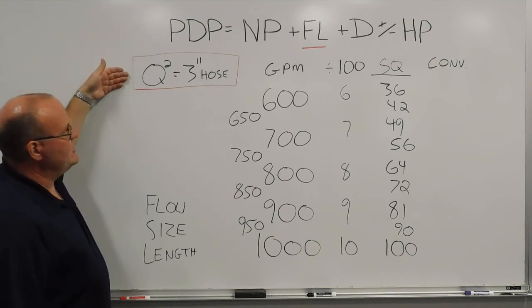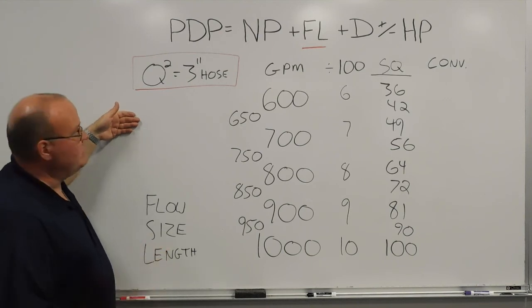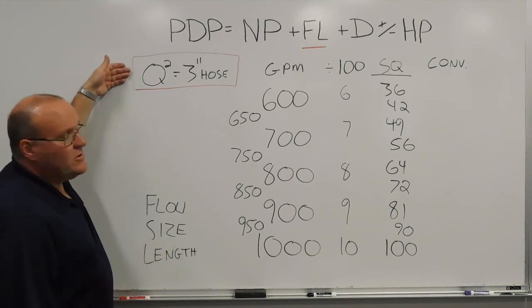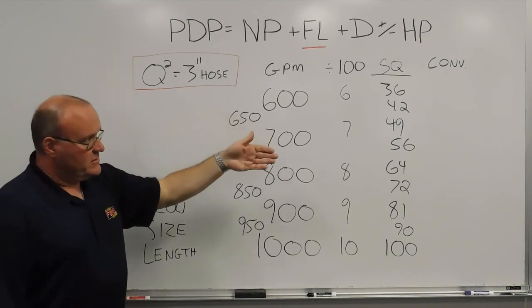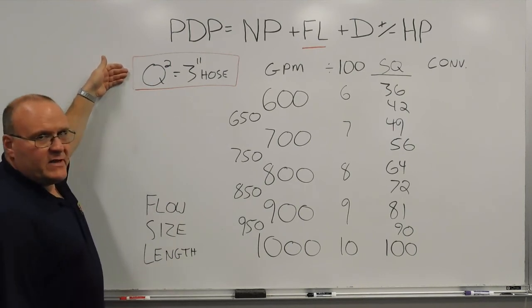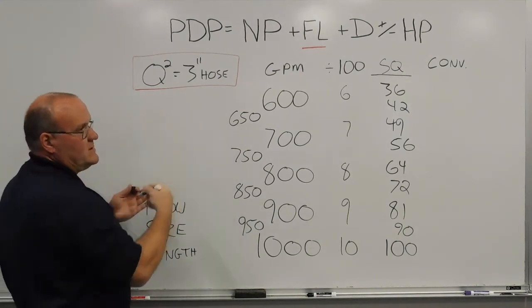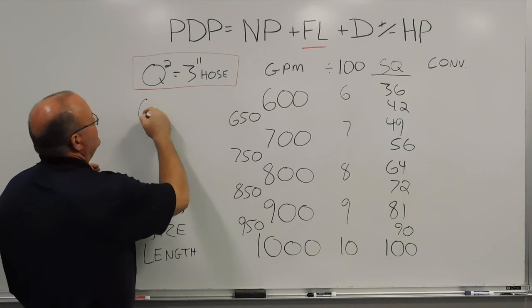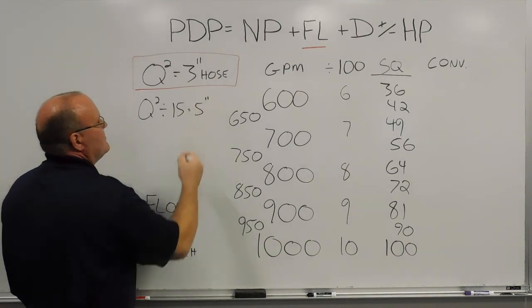When we went from 3 inch hose to 4 inch hose, hose size is bigger, friction loss decreases, we divided. So 3 inch hose to 4 inch hose was Q squared divided by 5. Now 5 inch hose, the friction loss is even lower, so we take that 3 inch hose number, Q squared, and we divide that by 15. So conversion factor, using this hand method, for 5 inch hose will be Q squared divided by 15, and that's your 5 inch friction loss number.